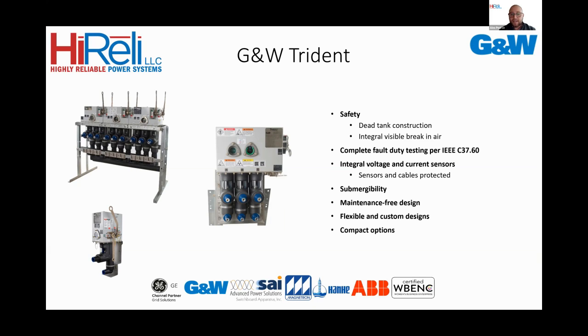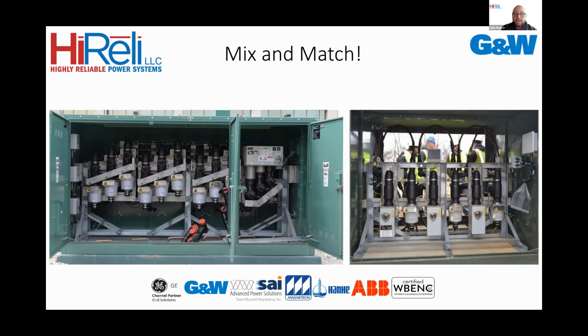And it has a 3-cycle operation speed. That's one of the newer products that's come out. So good for closed transition transfers. And then we can mix and match Vipers and Tridents. As you see in this pad mount on the left side, we have 3 Vipers bussed together with a single Trident. So that Trident can be used as a visible disconnect for all 3 of those Vipers.